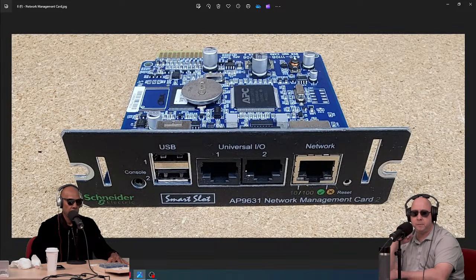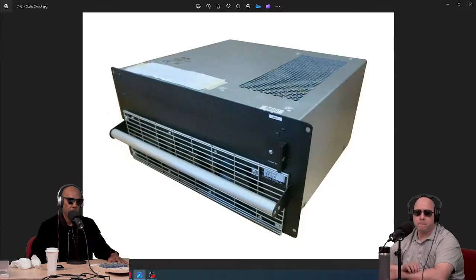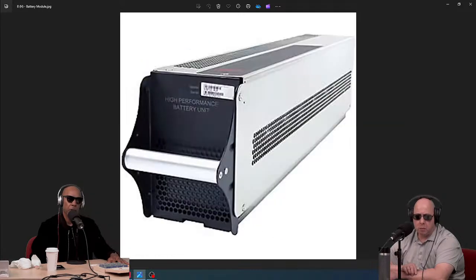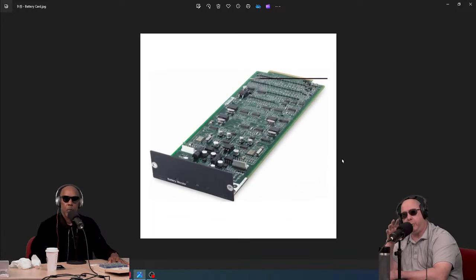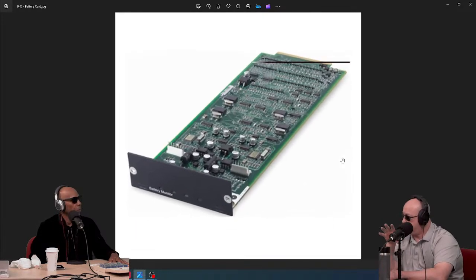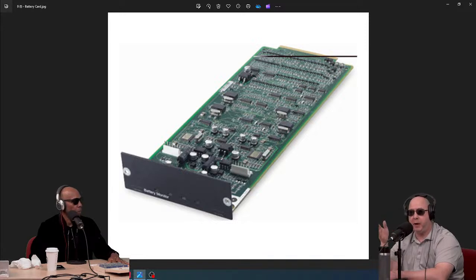All right, slide I, the battery monitoring card. There we go, that's it right there. Can you expand that a little bit? So what this does is, especially with an 80K frame, because there's no internal batteries to an 80K frame, you have to have a separate battery cabinet, or what they call XR, extended runtime. So this monitors the batteries that are in that battery cabinet. It also monitors the batteries within the system.